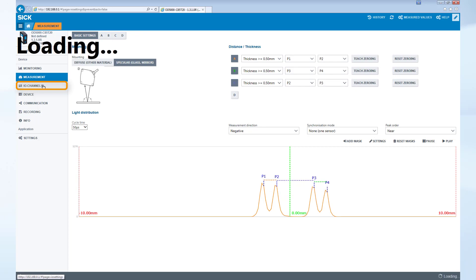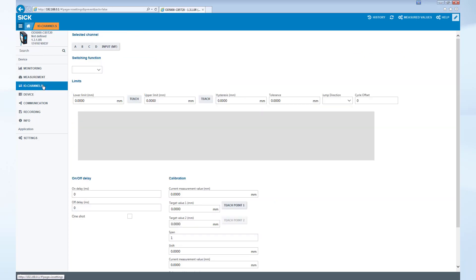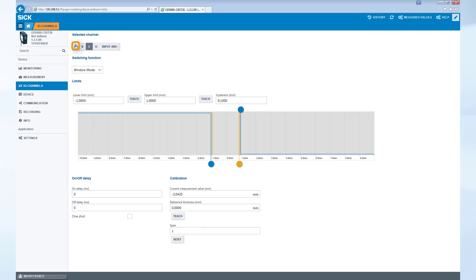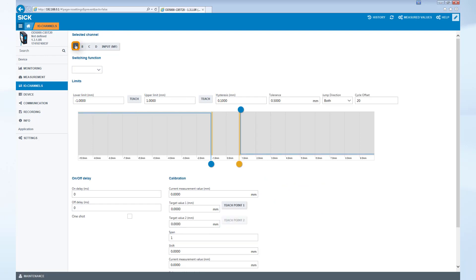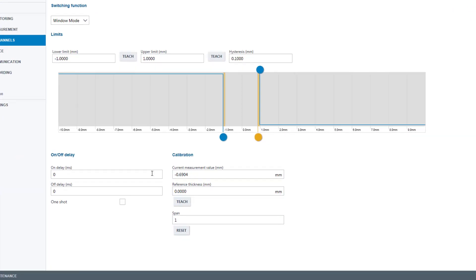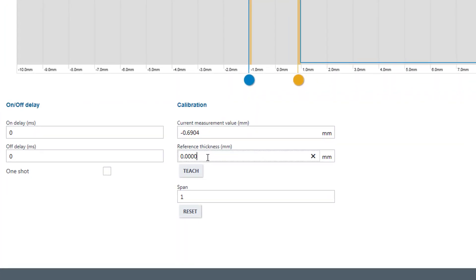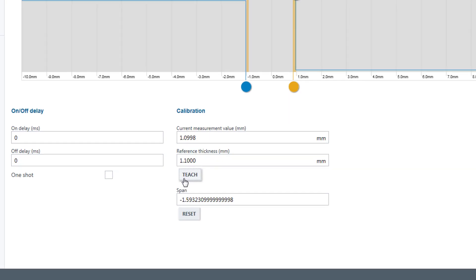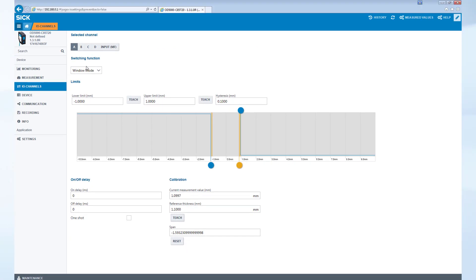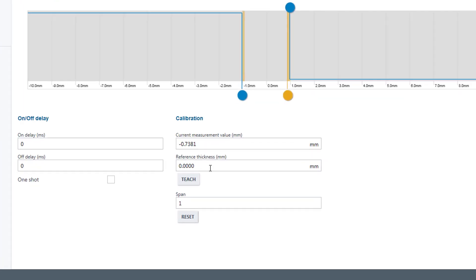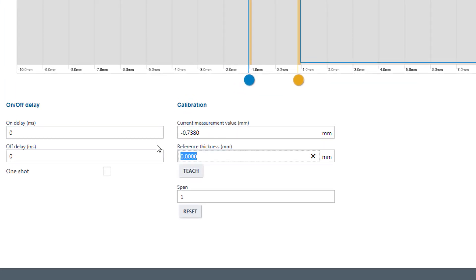To calibrate, we select I-O channels on the left side of the screen. Choose A for the thickness of the first glass target. Type the reference thickness into the input field, 1.1 mm in our case, and select Teach. Do the same for channel B for the second glass target.